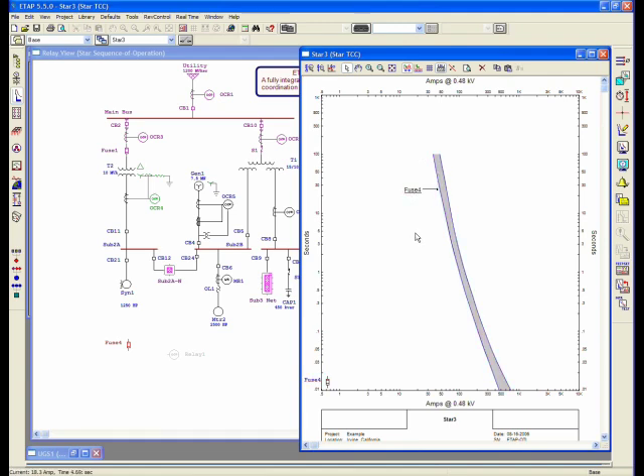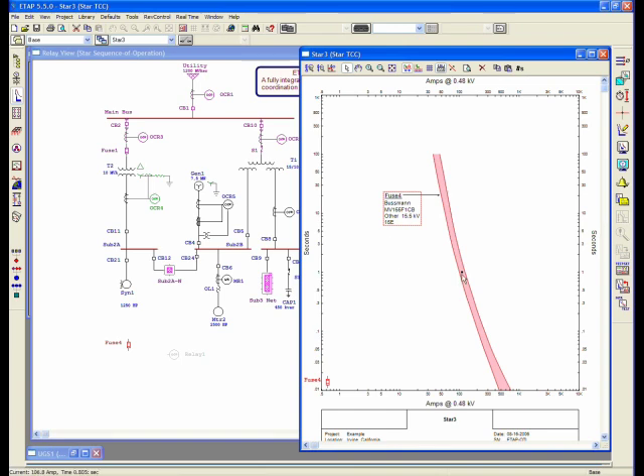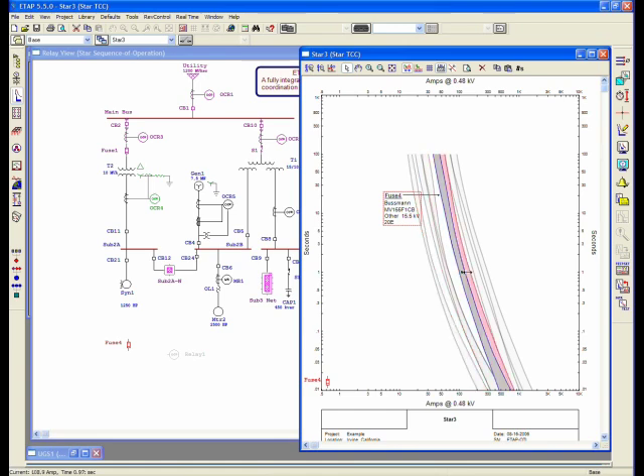This is my fuse 4, Bussman, MV15F1CB, 15.5 kV, size 15E. If you want to see the different ranges of this fuse, what you can do is there are tools provided in star view, and one of the tools is called Hide Ranges and Show Ranges. By just selecting on here, you can see all the other available sizes for that fuse, which you can coordinate with, or you can select. It's sort of a quick view for you to know what are the other sizes available.